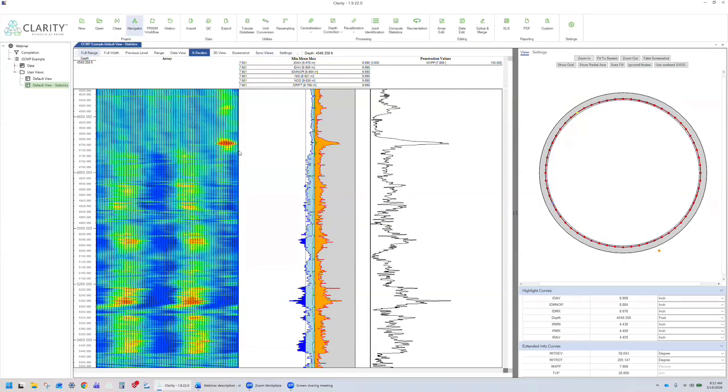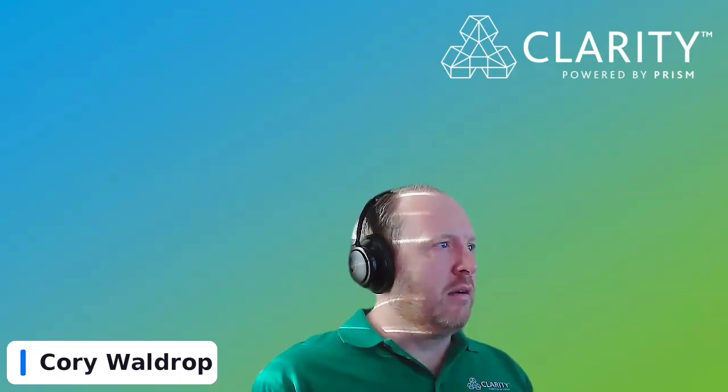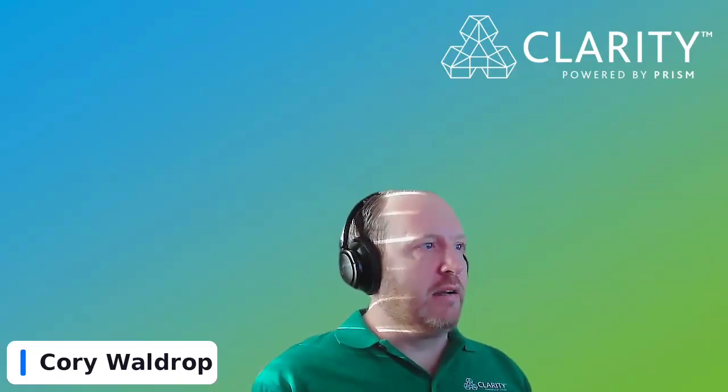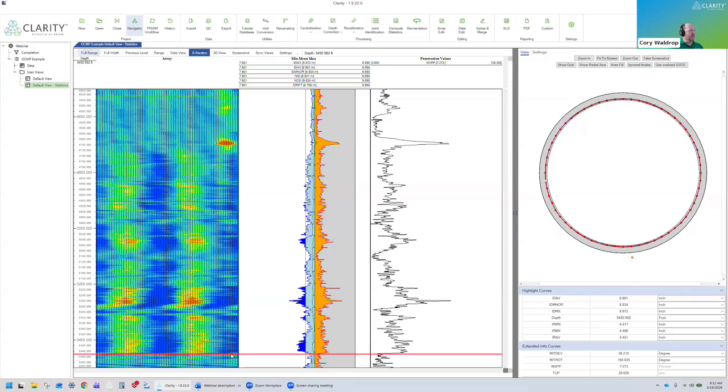All right. So yeah, this data set, I wanted to highlight the ovality compensated maximum penetration. That's the main feature I wanted to show. Anyone that's seen caliper data can recognize right away that we have ovality in this well, and not just one, it's over an extended period. And anytime we're trying to report accurate penetration values in an oval pipe, it's a nightmare because anytime you have an increase in your maximum recorded diameter, that's going to directly affect what penetration value is reported. Which you can see here, I've actually plotted the percent penetration curve.